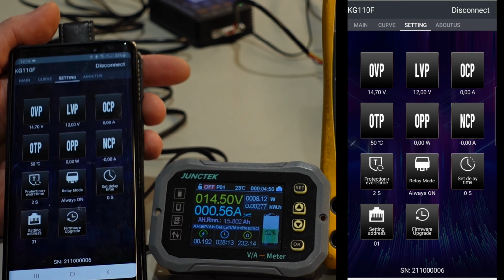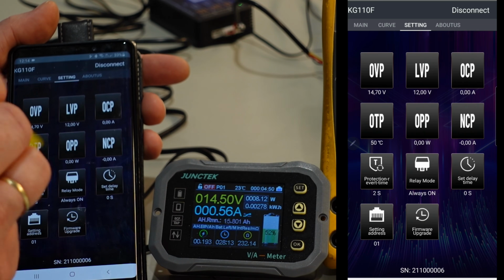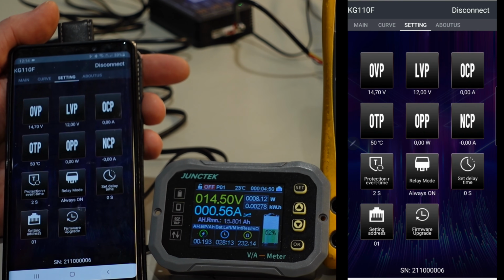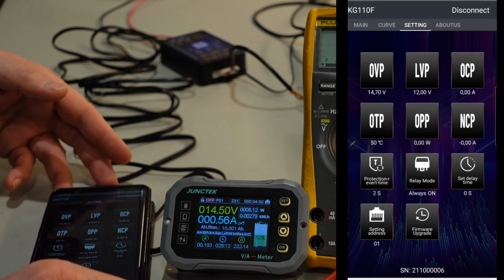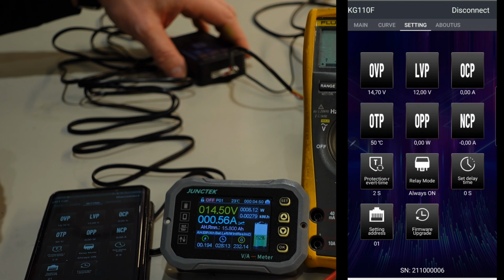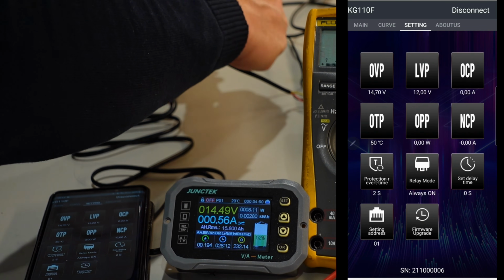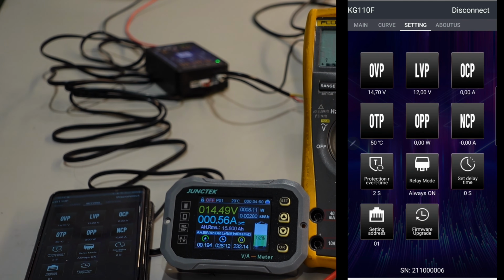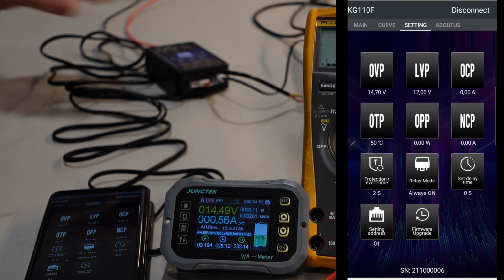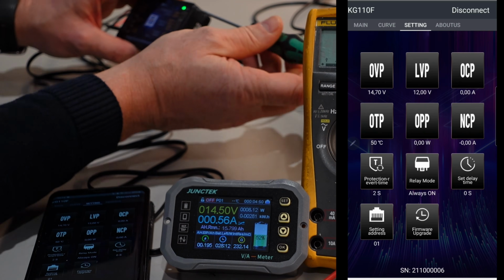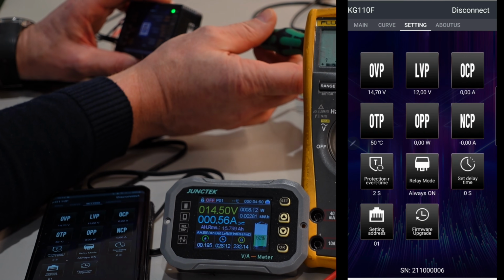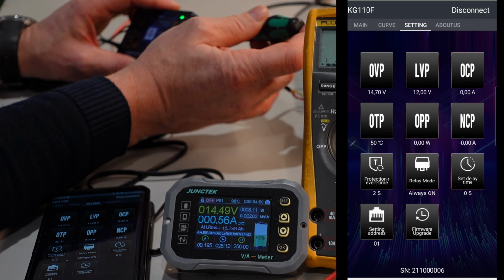If you press that button, you'll get a spinning circle and nothing will happen. To do the firmware upgrade, you have to disconnect the temperature probe, then use a metal object like a screwdriver to short circuit the 2 pins.